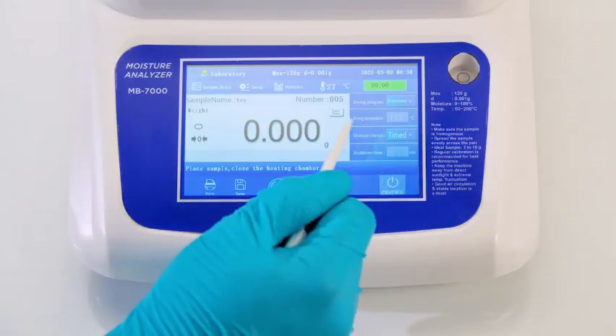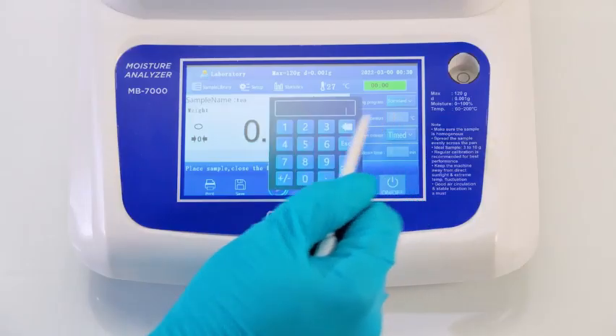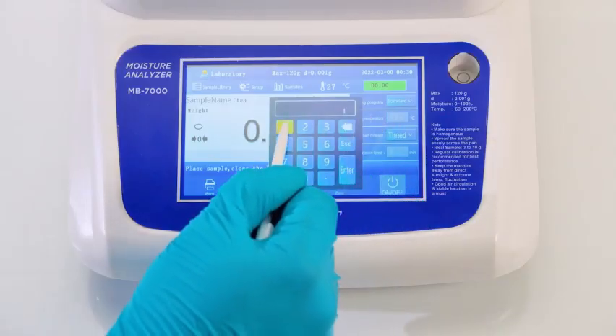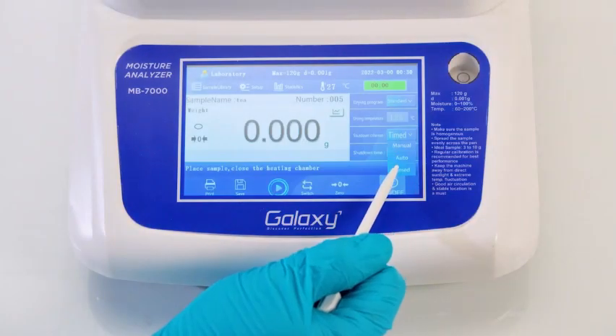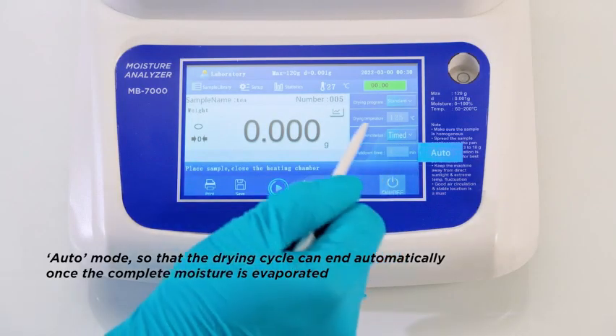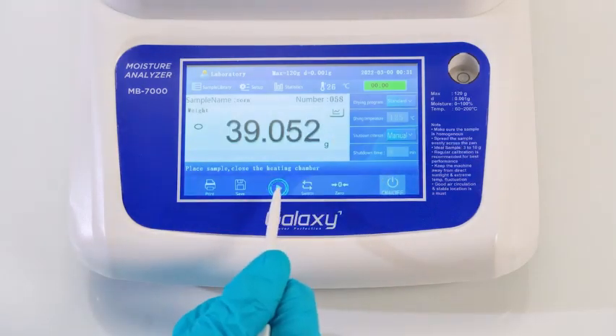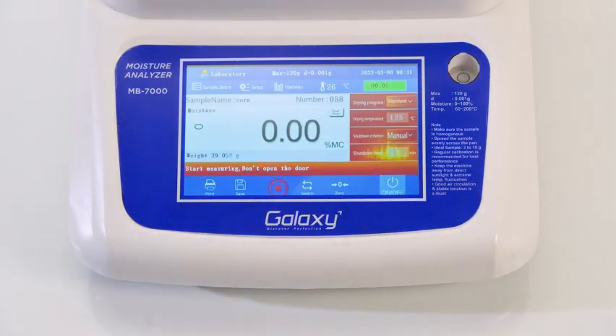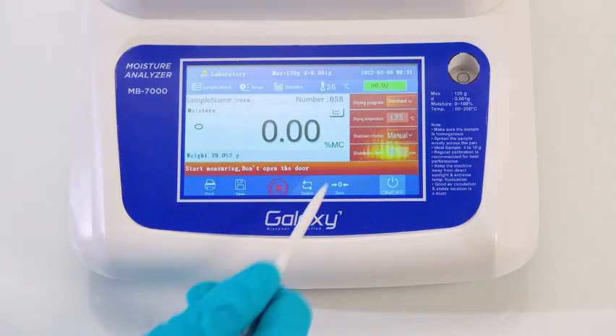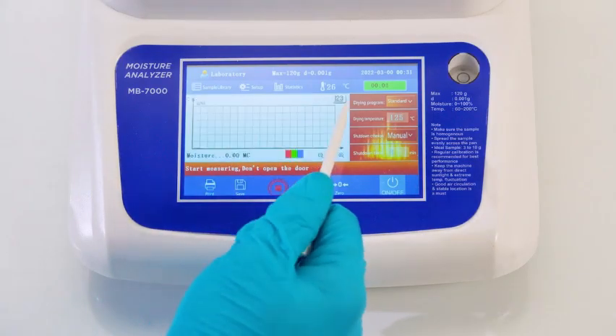First, we will set the drying temperature by clicking here. Input the desired temperature using the keypad shown on the screen. Now select the shutdown criteria by choosing from the drop-down menu. Click on Auto. Click the Run option to start the drying and measurement. Then, simply wait until the process is complete.